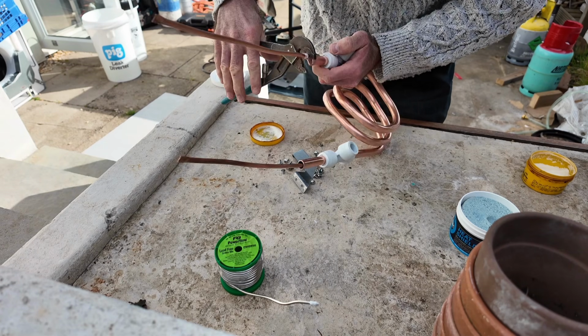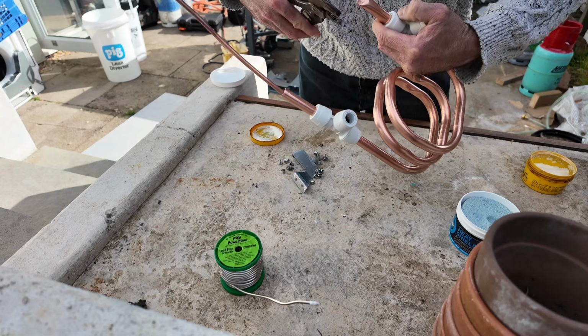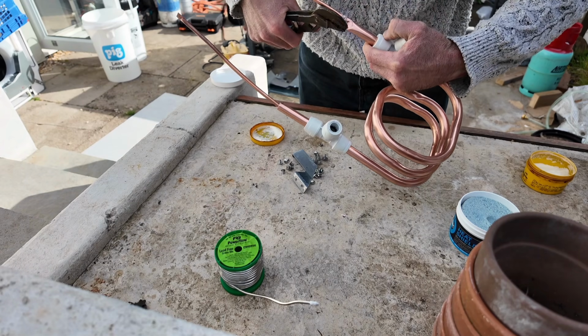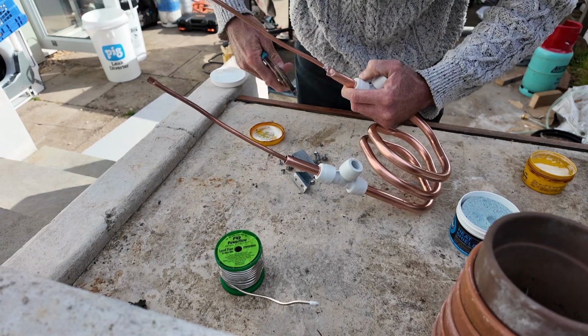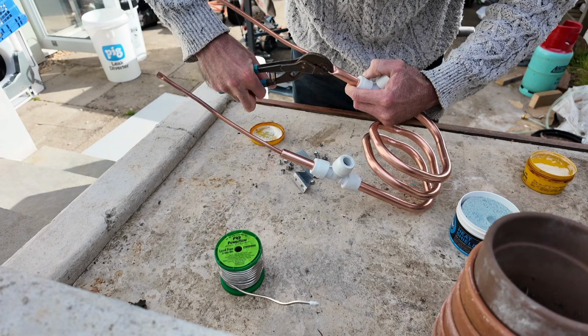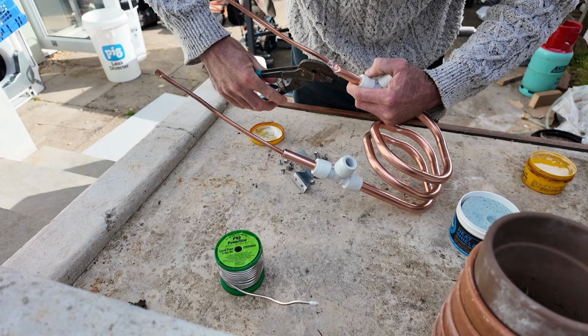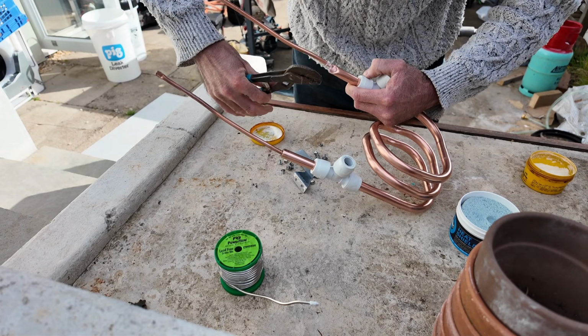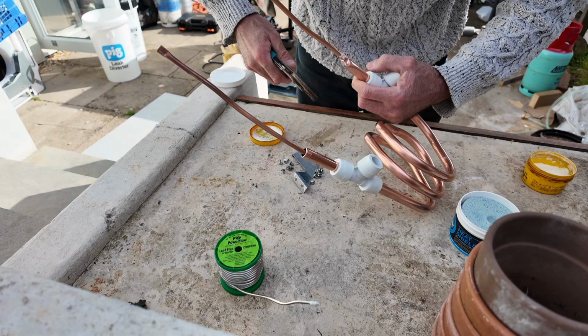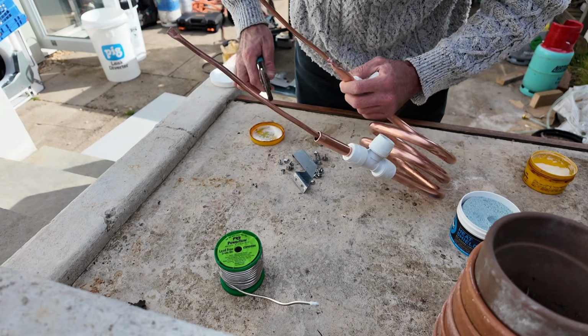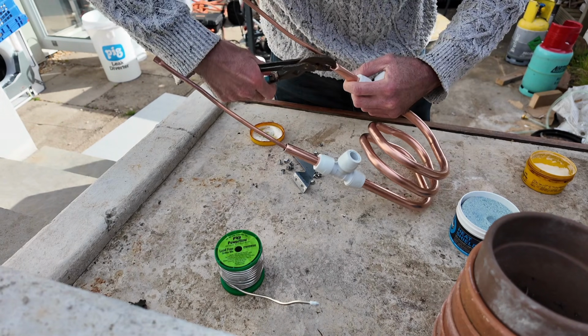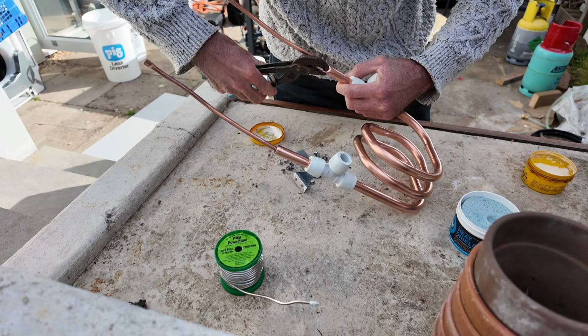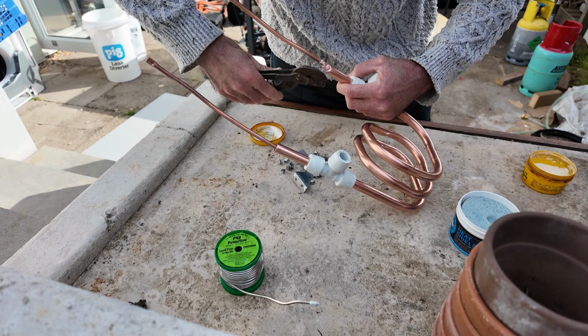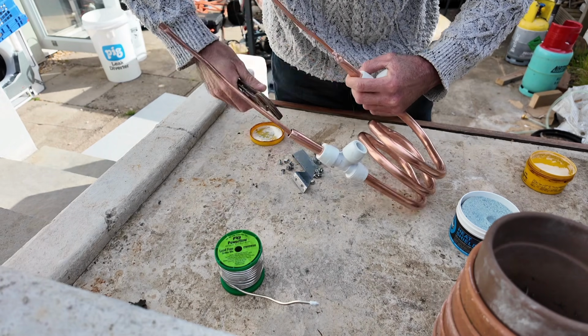Also, with the temperature warming up, where we're using a higher pressure refrigerant in a system that is not really meant for it, we're using R410 in an R404 compressor, just really because we can get a lower temperature with R410, but it is a higher pressure.